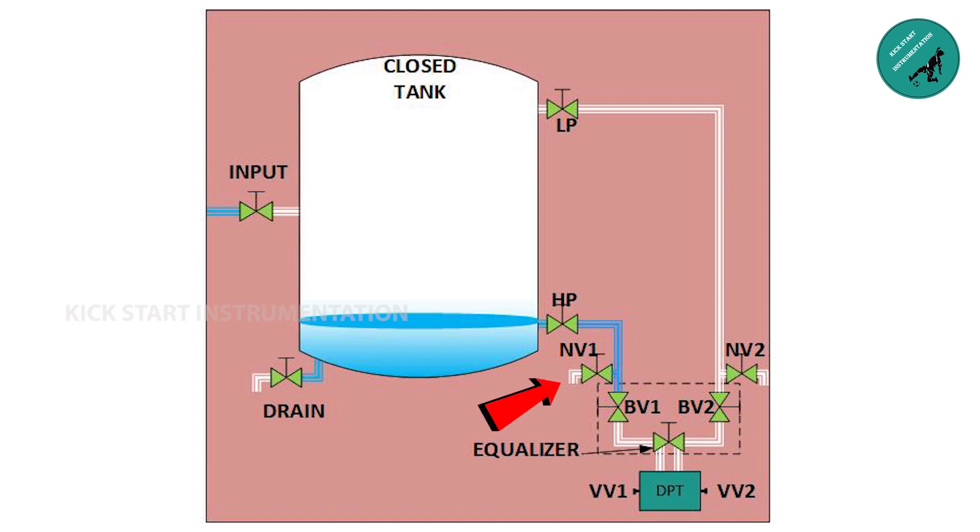The valves that are left closed after flushing will be needle valve 1, needle valve 2, block valve 1, block valve 2, equalizer valve, vent valve 1, and vent valve 2. High pressure SS tube is filled with process medium and low pressure SS tube is filled with gas of process medium after flushing.